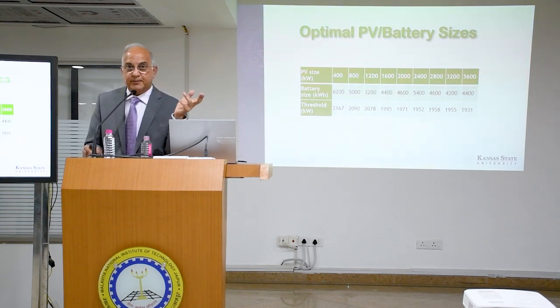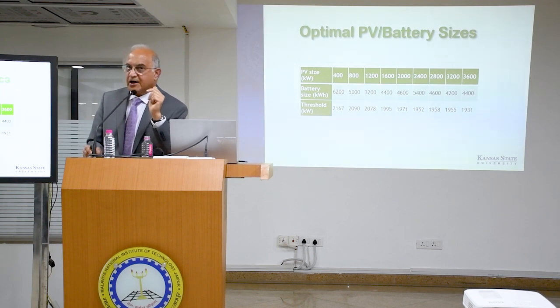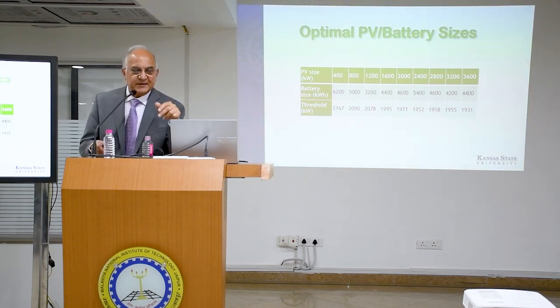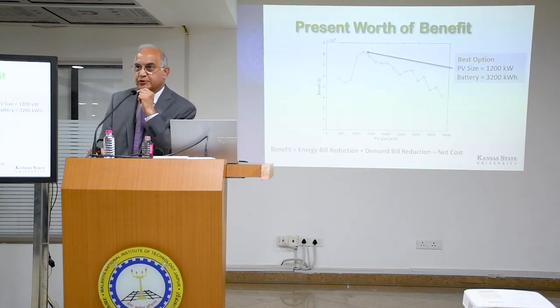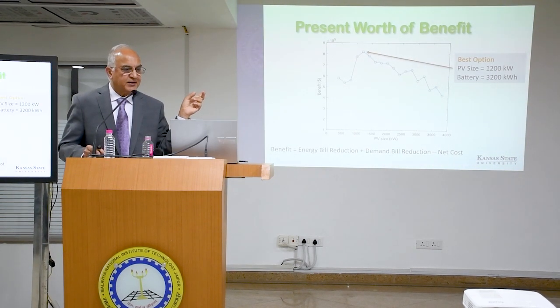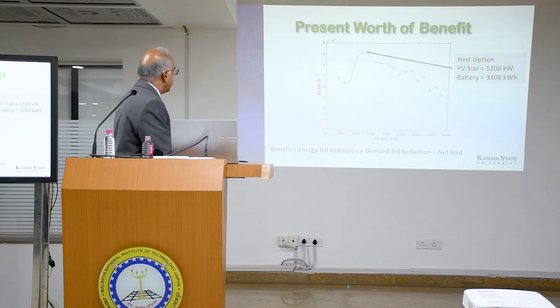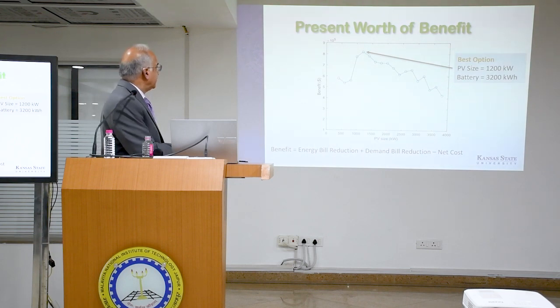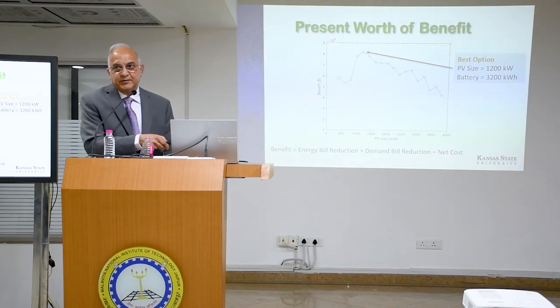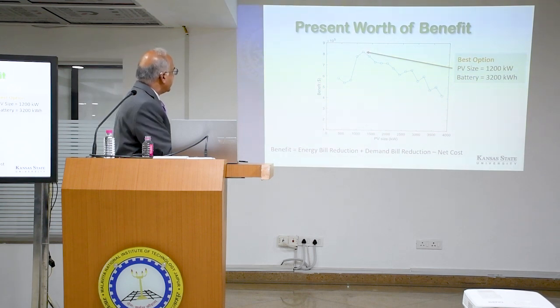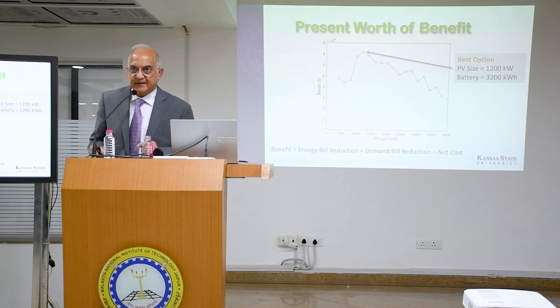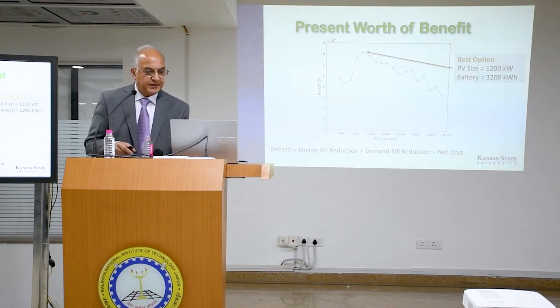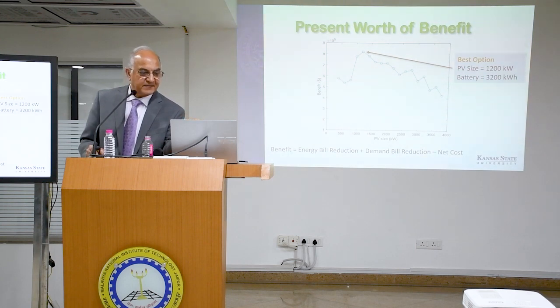And what we did is we created the present cost calculation. Now we have different combinations, so we can calculate the cost associated with them or the benefit. This is the graph you get for different combinations - PV sizes here, and the benefit there. You notice that as you increase the PV size, initially the benefit goes up and then it goes down. So this point right here is the best option. In this case, we have a PV size of 1200 kilowatts and battery size of 3,200 kilowatt hours.